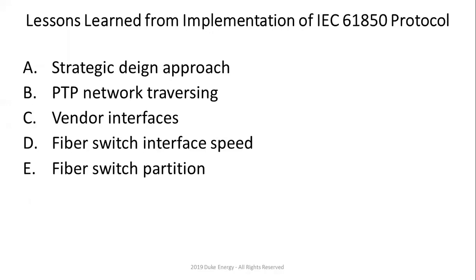Well, every relay doesn't need to hear everything, right? If you just put everything on one bus, then every relay is going to be hearing or seeing all of the data that it doesn't even need to see. Now, there's probably 6 or 7 megabytes per second of data, right? And I can tell you, if you put a Wireshark on all of the sample values coming in on our side for 10 seconds, you're going to get a file that's about 400 megabytes, right? So that's a lot, right? So what you want to do is some filtering. It's called MAC address filtering or something like that, right? So you want to make sure that your relay in the back only sees the merging units that you need to see, not every single merging unit, right?